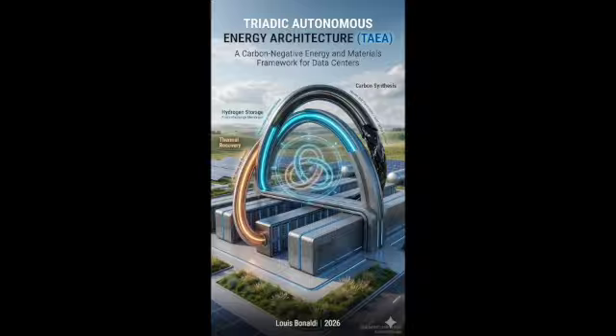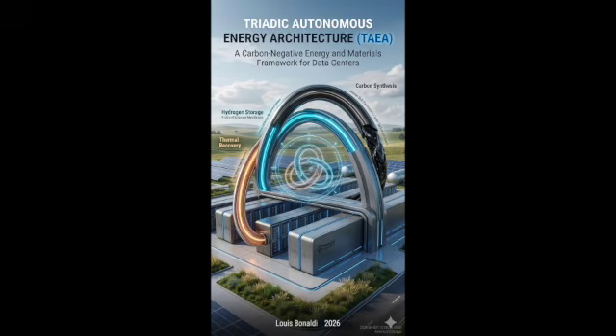So if System 1 is scavenging 10 to 12 megawatts and System 3 requires 5 to 10 megawatts to run the electrolysis, you are operating on a razor's edge, your energy ledger is incredibly tight. Very tight. But looking at the mechanics of these two systems, there is a colossal thermodynamic hurdle here. System 1 is scavenging heat from server exhaust, which is essentially just a lukewarm bath, maybe 35 to 70 degrees Celsius. But System 3 requires that salt bath to be molten.